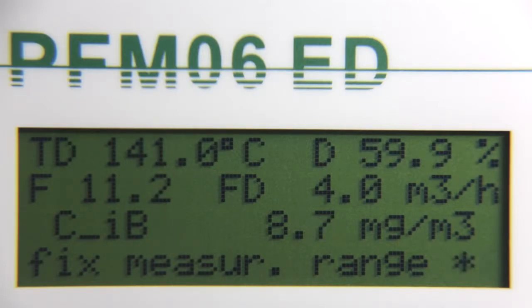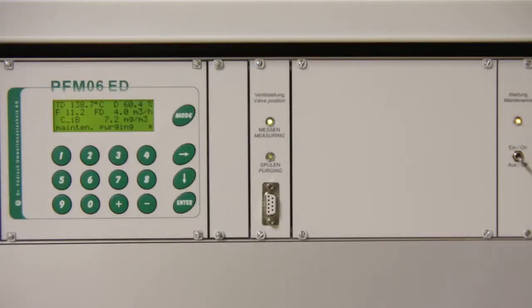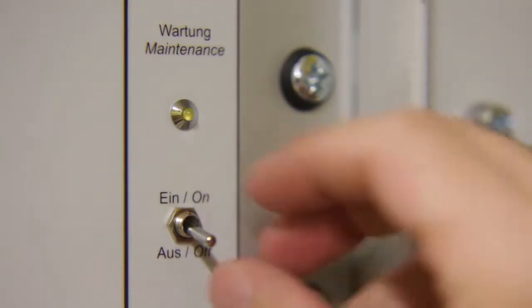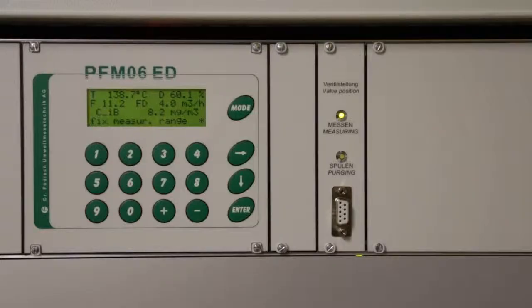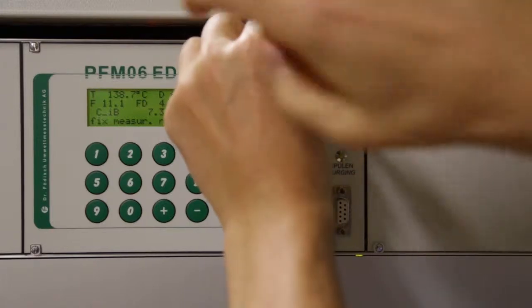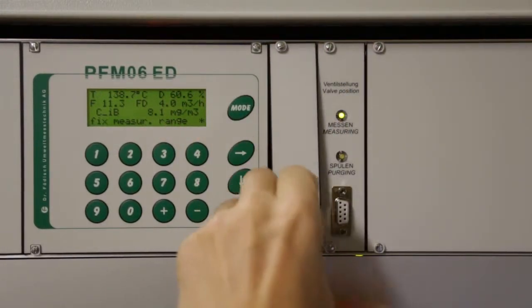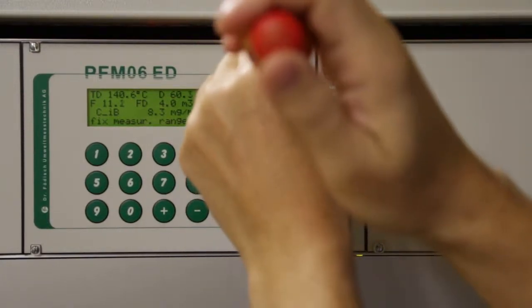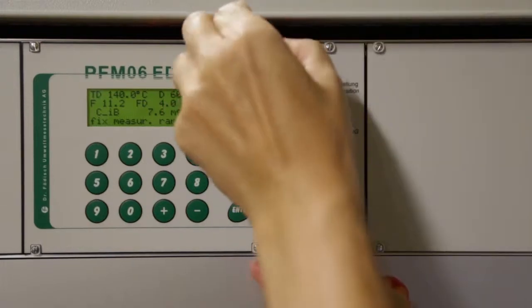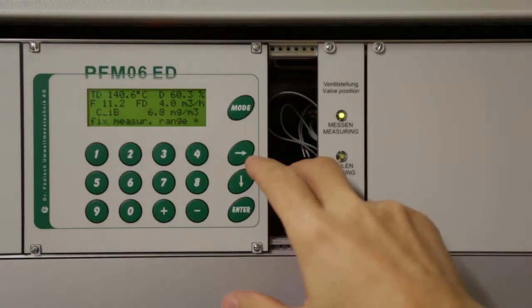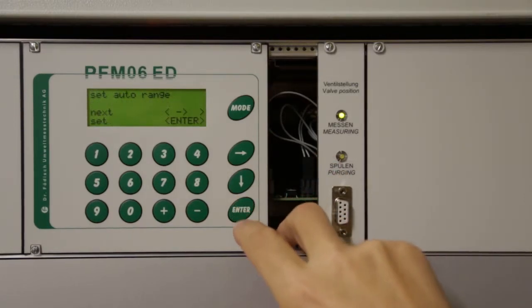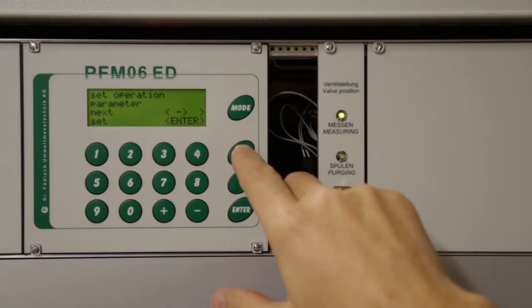The display of the control unit shows the most important values and current status information. You can switch between the modes measuring and purging. The maintenance mode of the PFM 06ED is shown at the LED maintenance. In order to check or change the settings of PFM 06ED, remove the cover next to the display and press the button inside. You can change the settings with the control keys. Here you can also enter the calibration factors after a gravimetric reference measurement.